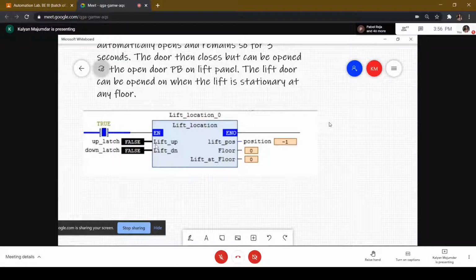The second way, instead of using an up counter and down counter, you can use an integral function, like the one used previously to simulate water level inside a tank - it's exactly the same idea. There, the level was increasing or decreasing; here, instead of level, it's the position of the lift changing, again from a minimum value up to a maximum value.